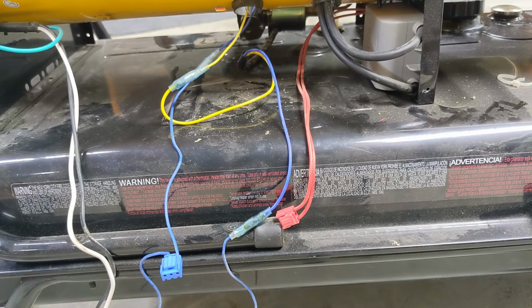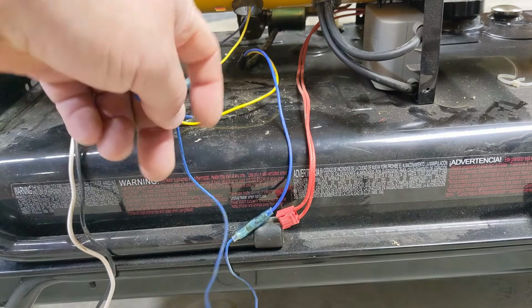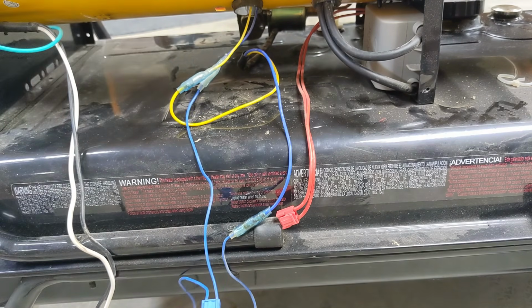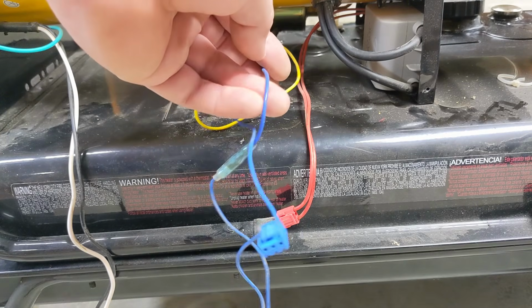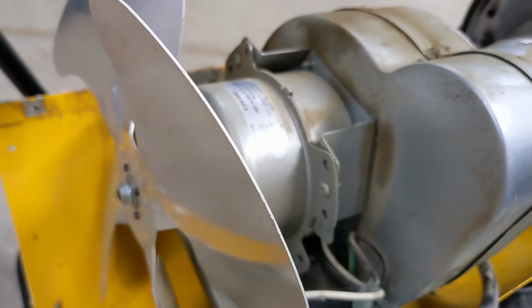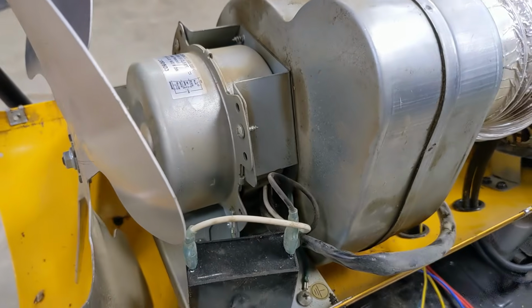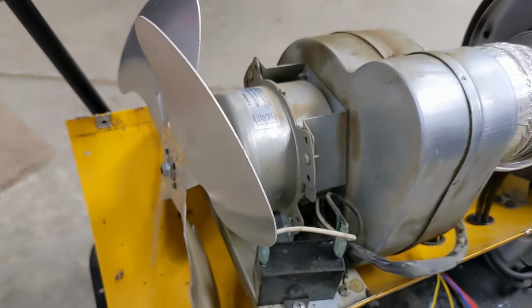And if that thermal protection kicks, it kills power to the fuel pump. And I'm not sure if it would to the motor also. But anyway, the point is, these wires go through that thermal overload sensor. One wire goes over to the fuel pump. The other one goes up here inside the motor housing. I'm going to take that screw off and see what the wiring is inside the motor case. Let's see what's in there.